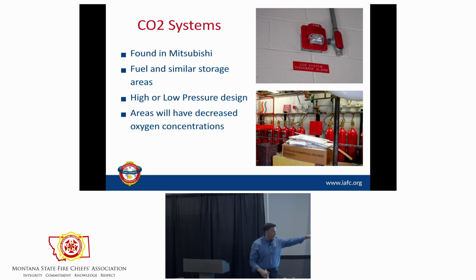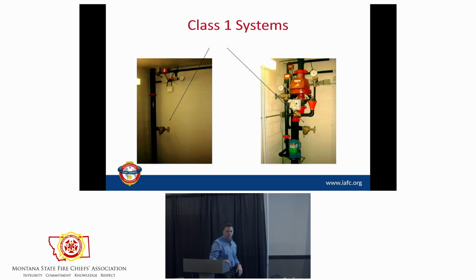When you dump a bank of CO2 like that into a room, it's going to take away the oxygen. So when we go in, check the fire alarm control panel first. If it says CO2 system activation, somebody better go back and get your 4 or 5 gas monitor and carry it with you. Better yet, it will move outside the room, and you're not going to know it, and all of a sudden you'll have it. All right?